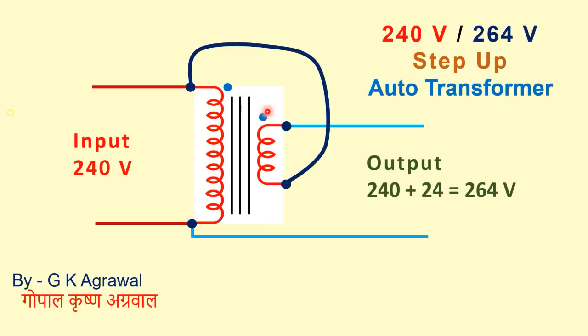This has become step up auto transformer 240 volt by 264 volt. I have made only one extra connection, this one. If we give here 240 volt, here we will get 264 volt, 240 plus 24 volt. This output is more because in the output this winding and this winding are added. There is no isolation in this transformer in between input and output.